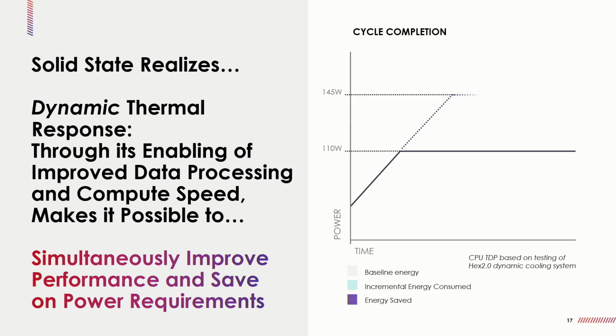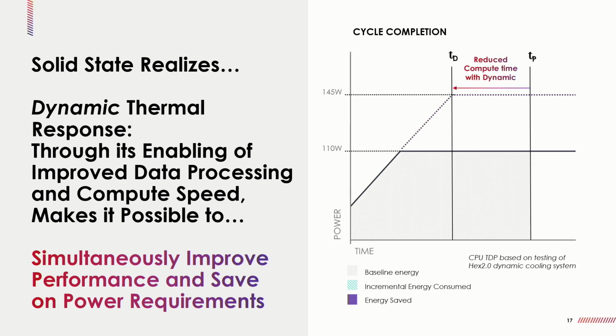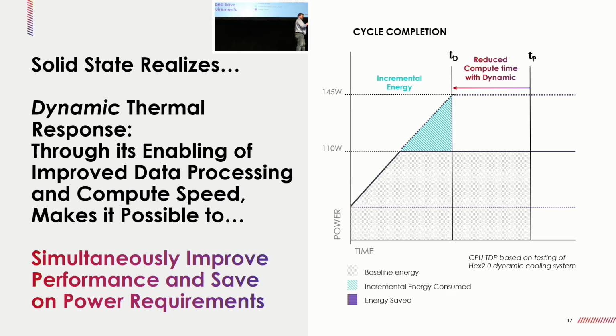But when you enable dynamic cooling, you create a new paradigm. You essentially allow for an incremental increase in power consumption, but what you look at is the difference between the time passive and the time dynamic to complete the compute cycle. And even taking into account this power that you used to maintain this performance profile, at the end of the day, when you compare the passive compute profile to the dynamic compute profile, you have a net energy savings because you complete your cycle and you're no longer using that base load of energy.